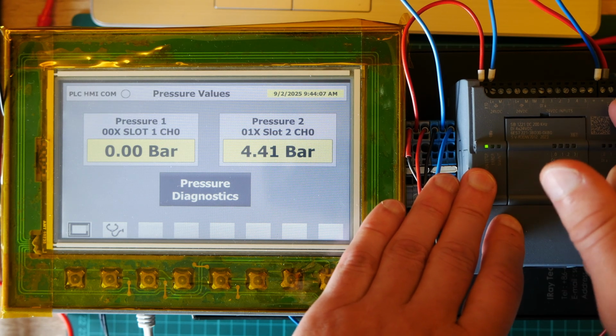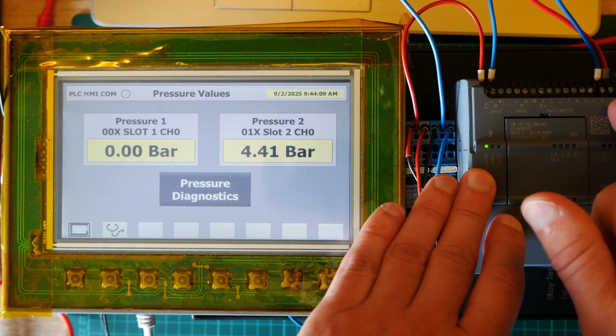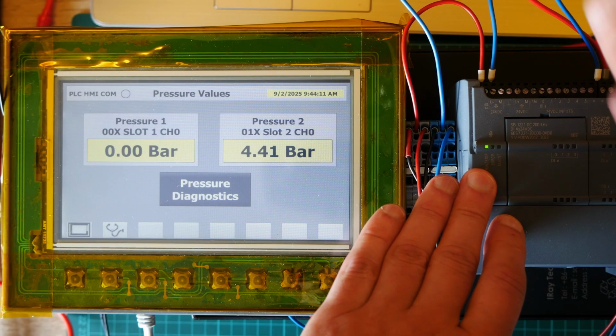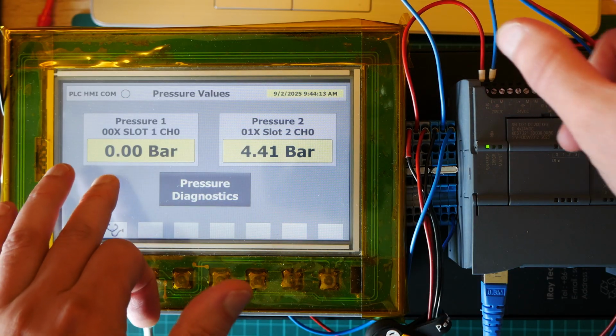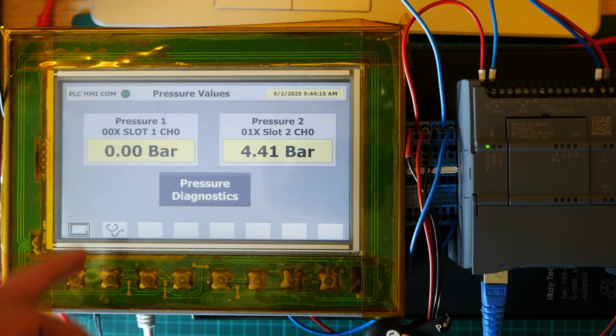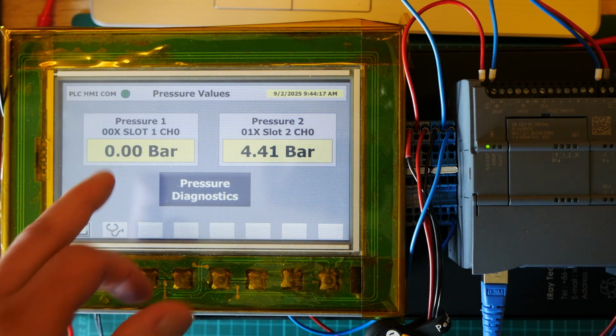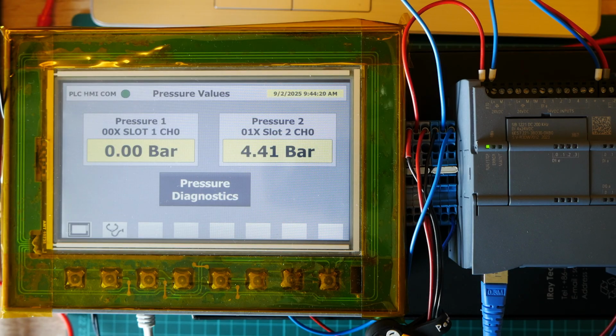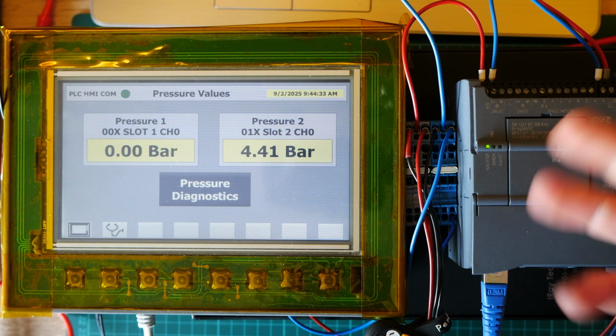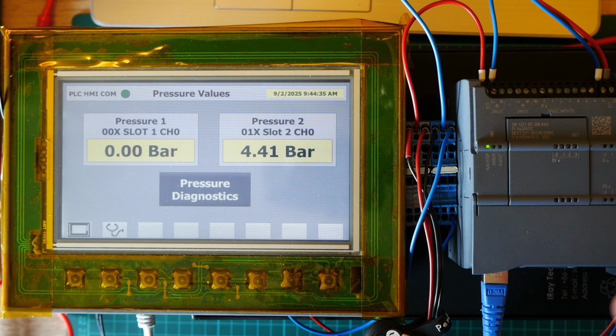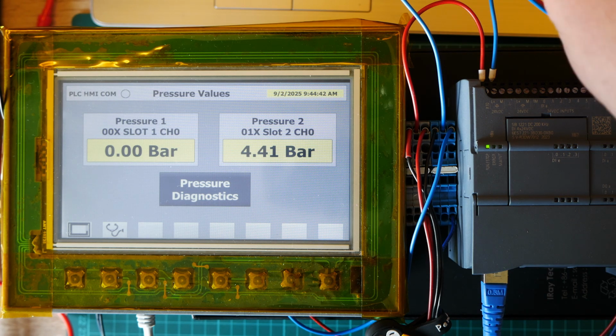Maybe it's damaged somehow internally, something going on. With the cables removed, it should show 0 bars. If it doesn't, you need to ask your PLC programmer for help and figure out what's going on. But most likely the problem will not be in the program or in the analog input side, because that is very rare.